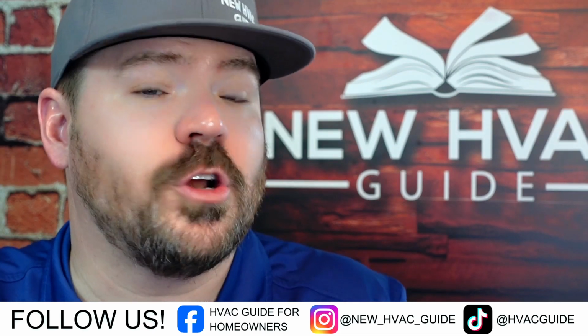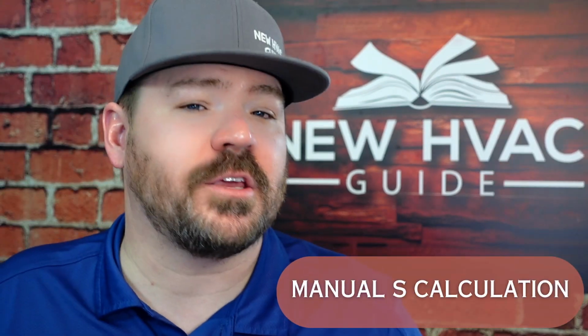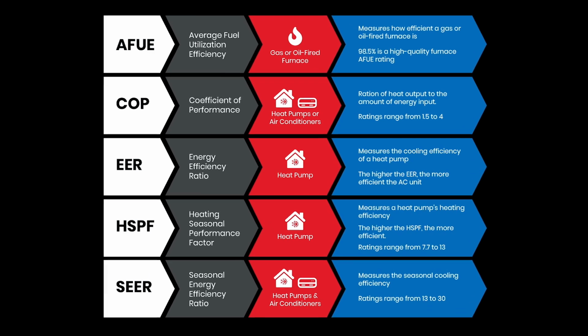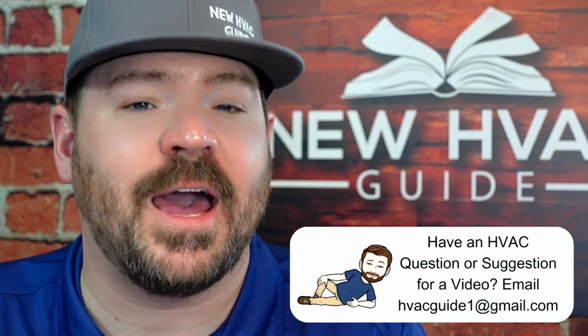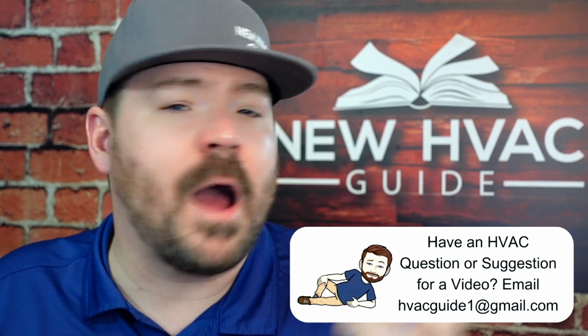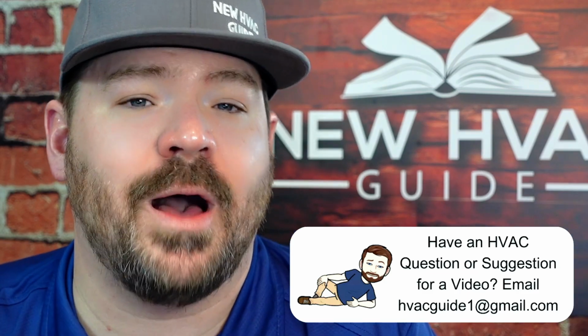Finally, the third calculation that's important and overlooked way too much in our industry is a Manual S calculation. This calculation ultimately helps you decide what equipment works best for that application. It takes all kinds of things into account — where you live, what type of system you're installing, and ultimately sizing as well. A lot of folks don't realize a 3-ton system is not always equal to a 3-ton system. Looking up the ratings and understanding what works best for that application matters — there are ducted and ductless systems, inverters and non-inverters, water-to-air type systems, all kinds of systems out there. Deciding what works best for that home is sometimes the big deciding factor not only on how comfortable you are and how well that system operates long term, but ultimately how efficient it is and how well it gets the job done.